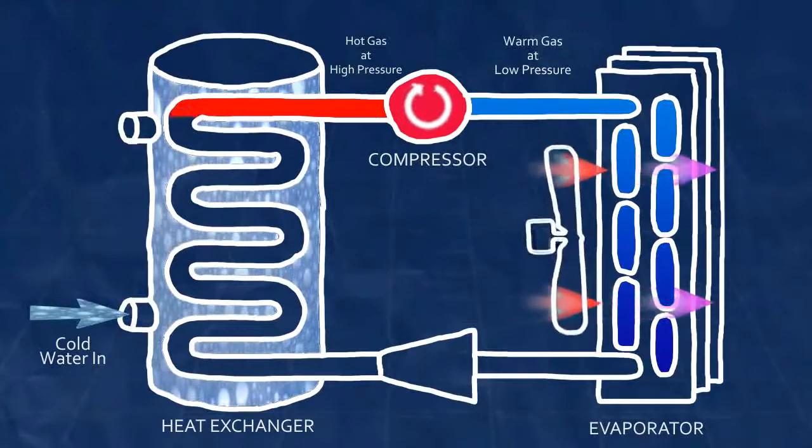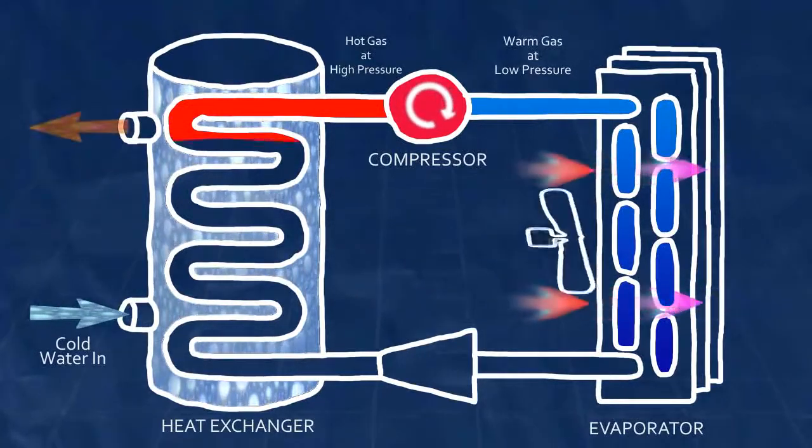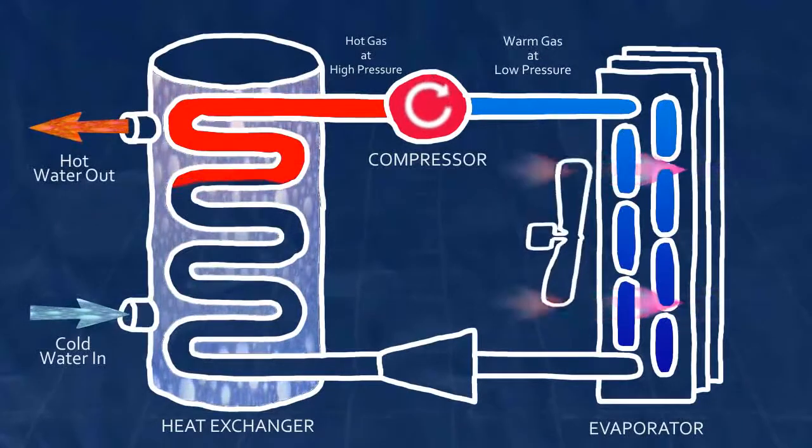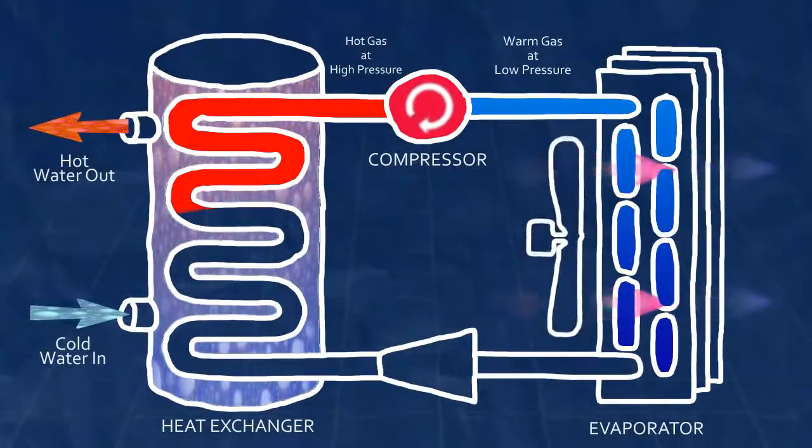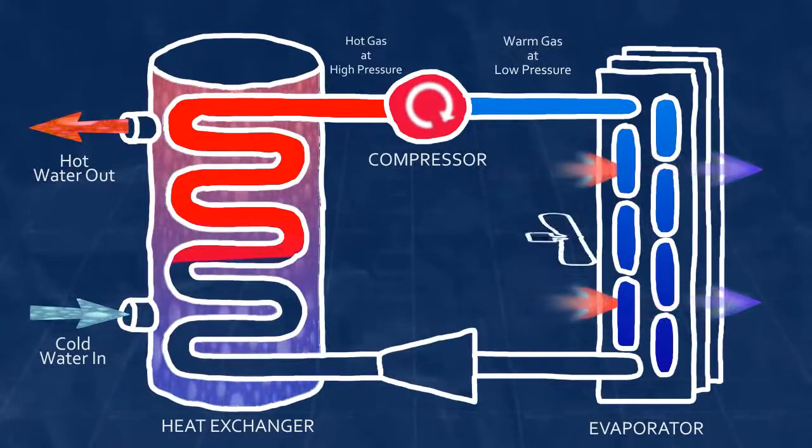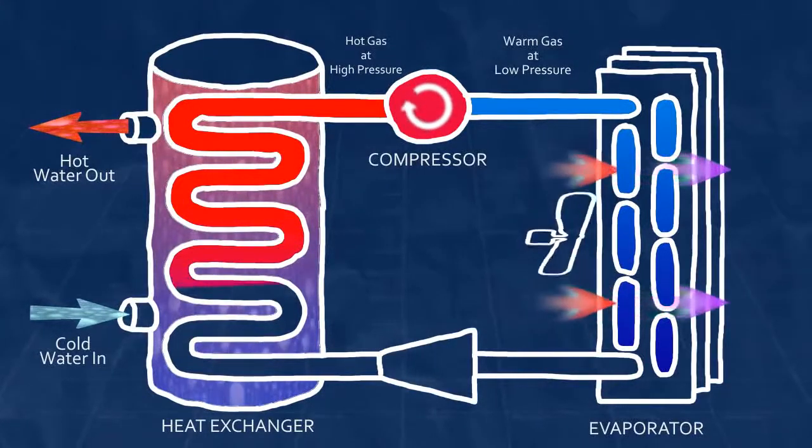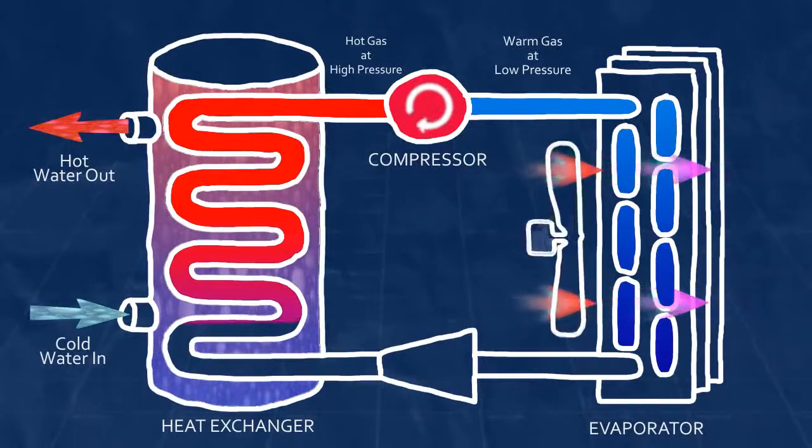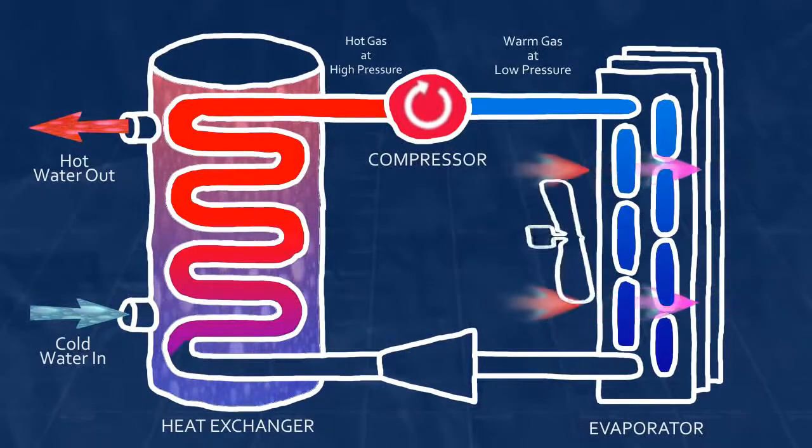The condenser is in contact with the water and the hot gas now gives up its heat to the colder water. As heat leaves the gas refrigerant, it cools off below its condensation point and changes from a gaseous state to a high pressure liquid state. The change from gas to liquid facilitates the large transfer of heat energy to the water.